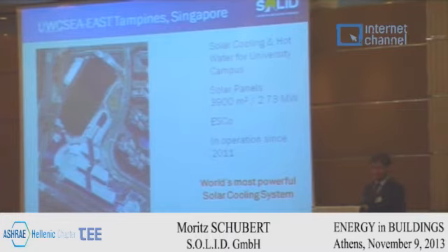This was quite a challenge, but we managed it. Now the solar heat goes from the collectors to two tanks of 60 cubic meters, and then to the absorption chilling machine or to the domestic hot water. It's now been 2 years in operation and it works quite well.